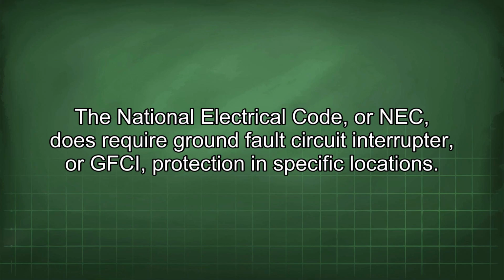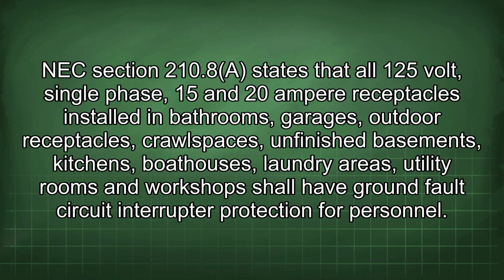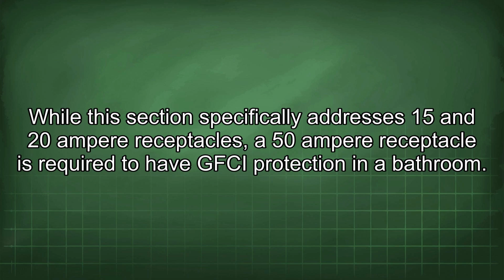The National Electrical Code, or NEC, does require ground fault circuit interrupter, or GFCI, protection in specific locations. NEC Section 210.8 states that all 125-volt single-phase 15 and 20 ampere receptacles installed in bathrooms, garages, outdoor receptacles, crawl spaces, unfinished basements, kitchens, boathouses, laundry areas, utility rooms and workshops shall have ground fault circuit interrupter protection for personnel.